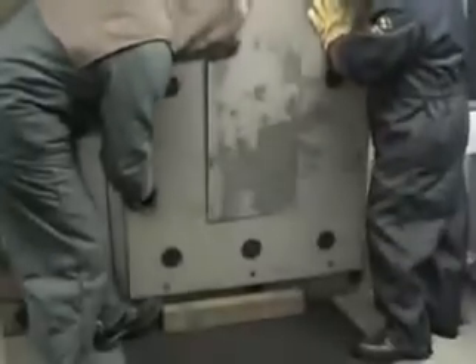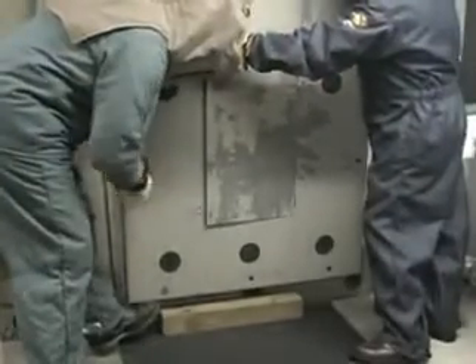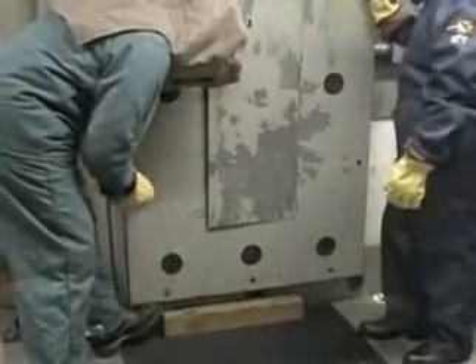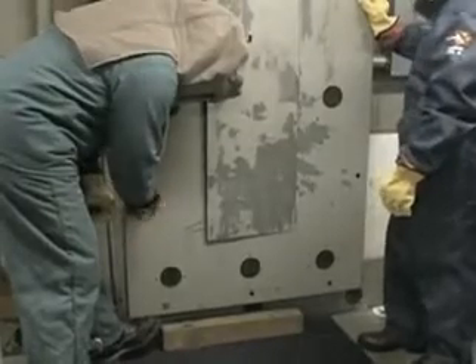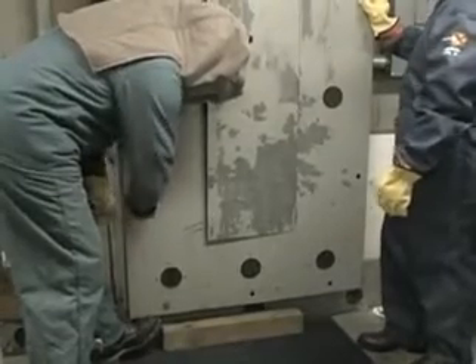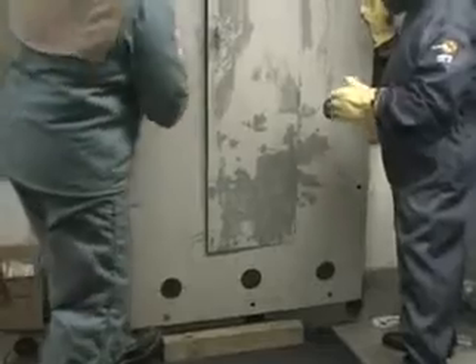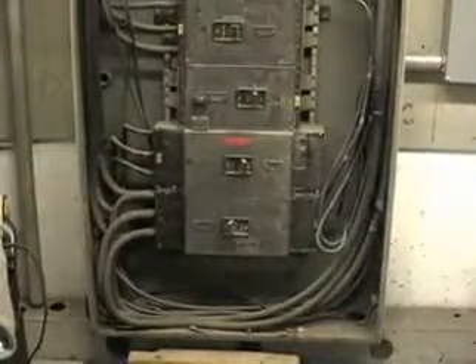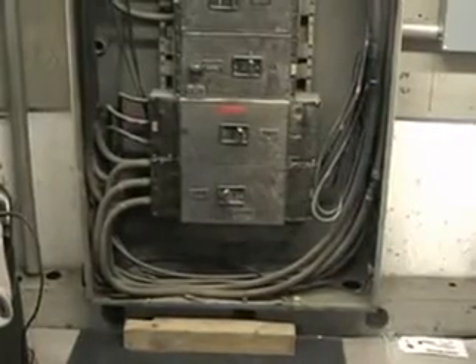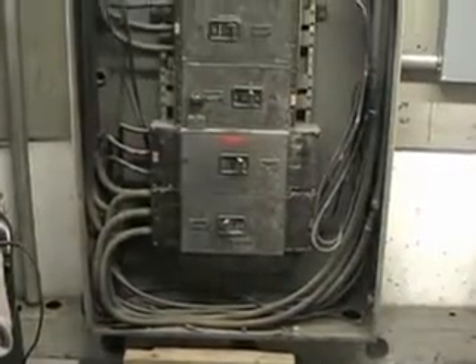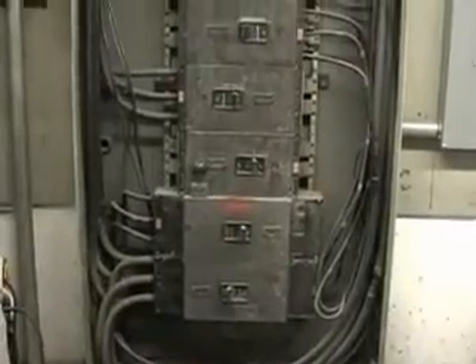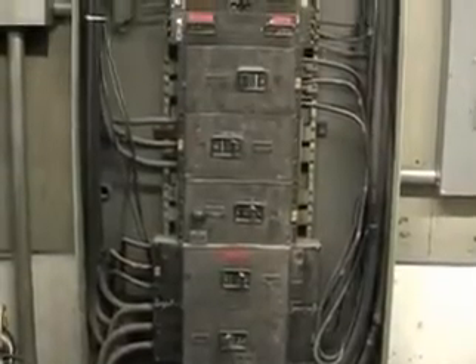After completing an entire scan with the ultrasonic probe, the technicians safely remove the cover. As you can see, performing electrical preventive maintenance is a two-person job. After removing the cover, we perform a visual inspection to identify code violations and any potential safety or performance risks. All the findings will be again documented in the TEGG tasking software.